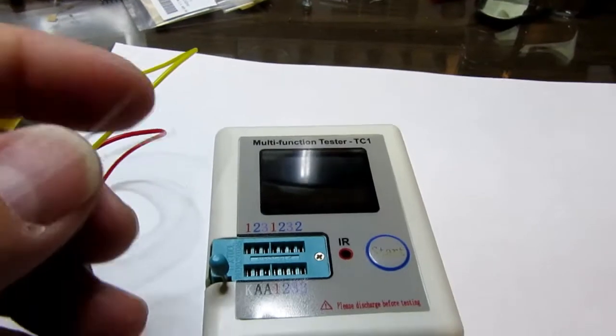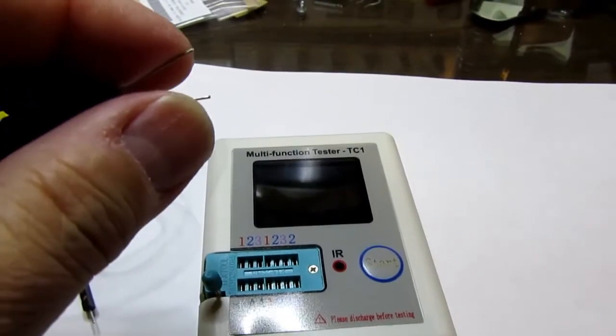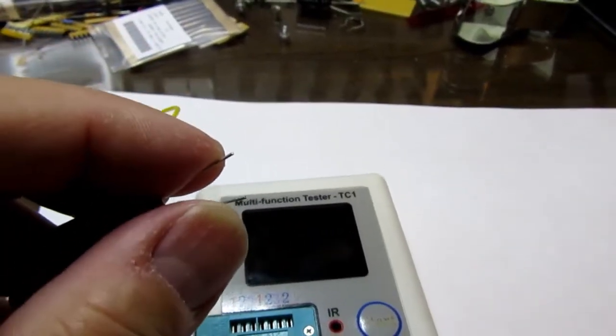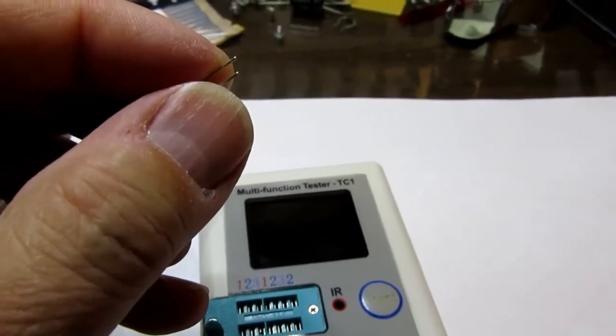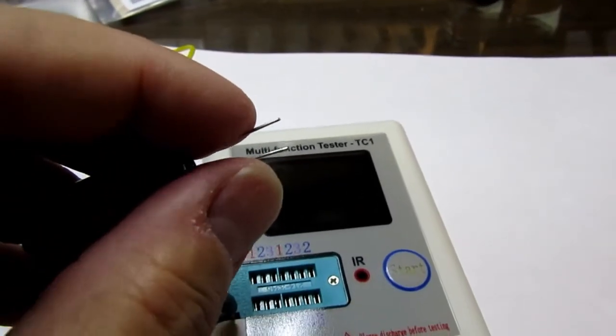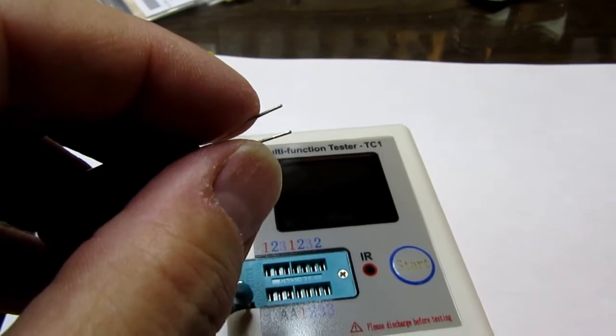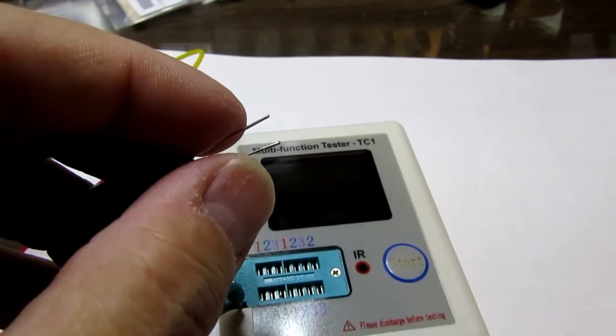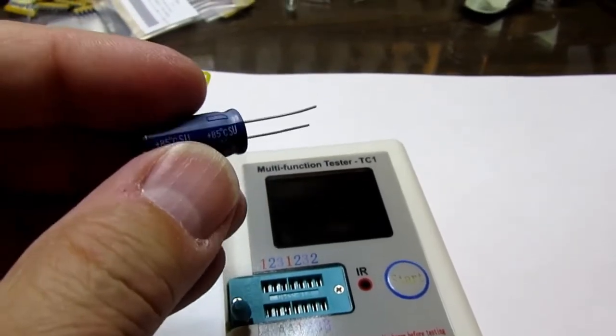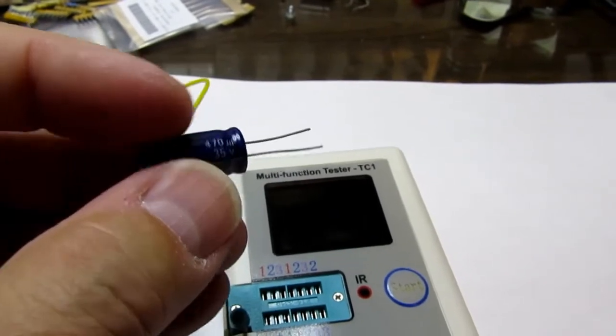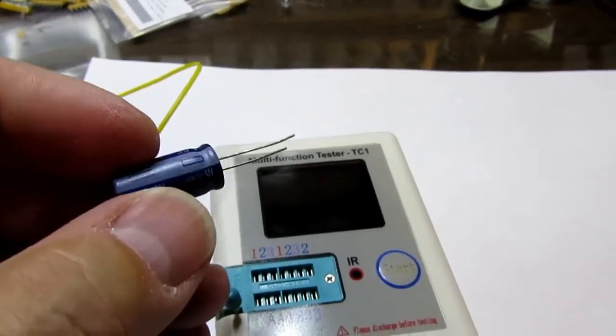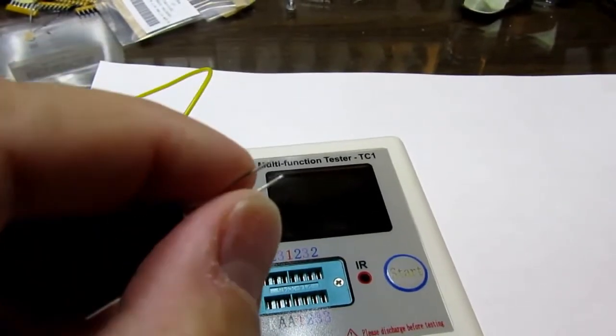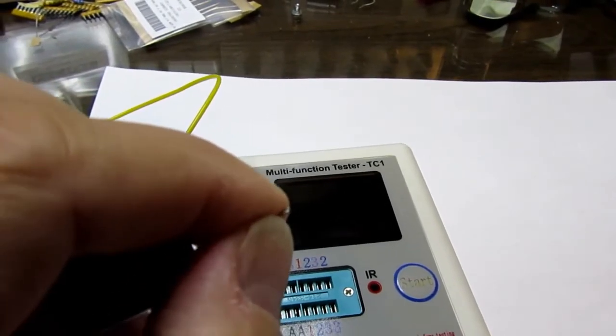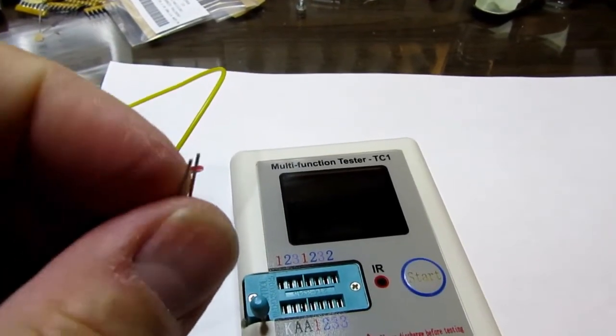The documentation I found online, which was hardly a manual but at least some advice, notes it doesn't apparently have much protection against over voltage or reverse voltage. So the only components this tests which would have a voltage on them when they're not connected to the tester would be capacitors, so it's advised to touch the leads together before plugging them in.